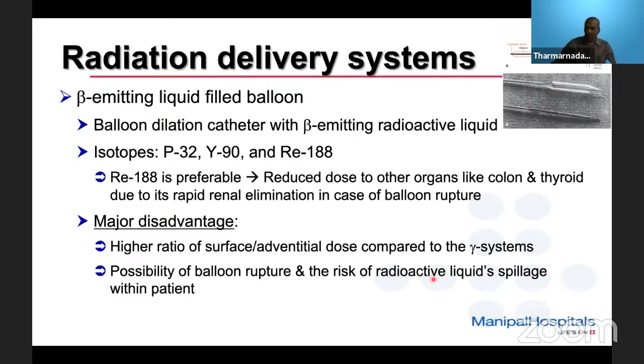But the major disadvantage with this type of balloon filled with beta emitting radioactive liquid is the higher ratio of surface to adventitia dose compared to the gamma system. That is, at the surface, what is the dose, and at the adventitia, what is the dose? The ratio of the surface to adventitia dose is very high with this type of beta sources. I told you, in the target region, beta sources produce non-uniformity, whereas gamma systems produce uniform doses. Possibility of balloon rupture is there, and the risk of radioactive liquid spillage within the patient is always there.